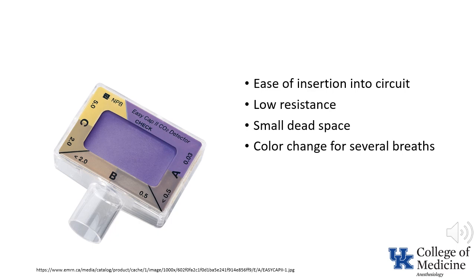The desirable characteristics of a colorimetric CO2 analyzer should include the use of a stable dye which results in a rapid color change that is not red-green, because approximately 8% of the male population is red-green colorblind. The indicator should not be affected by nitrous oxide, volatile anesthetic agents, or water vapor. Obviously, a colorimetric device is difficult, if not impossible, to read in the dark. It is common on oral board questions to ask whether a colorimetric device is a suitable substitute for quantitative capnometry during an anesthetic — the answer is that it is not.